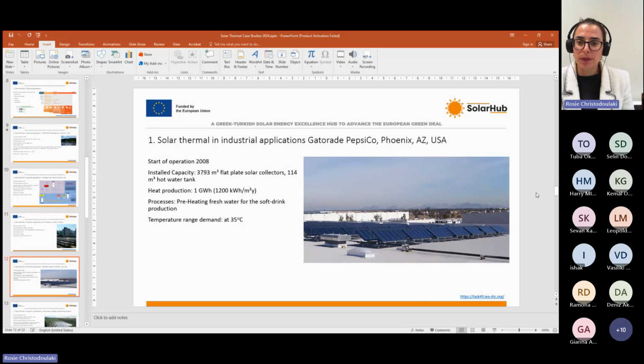In this solar thermal system, it is also an industrial application. It is based on the roof of the Gatorade PepsiCo factory in Arizona, in the USA. It started operation in 2008, and it consists of approximately 4,000 square meters of flat plate solar thermal collectors, and has also a big hot water tank, not one obviously, but several, that all add up to 114 cubic meters of hot water. The annual heat production is estimated at 1 gigawatt-hour thermal.